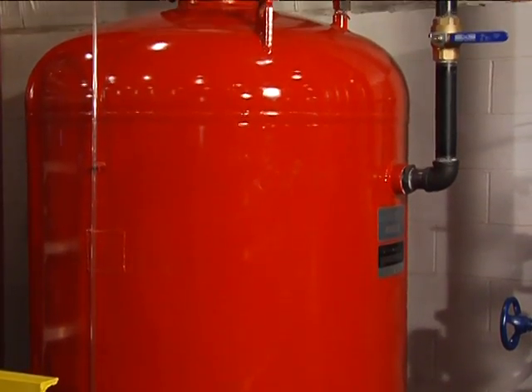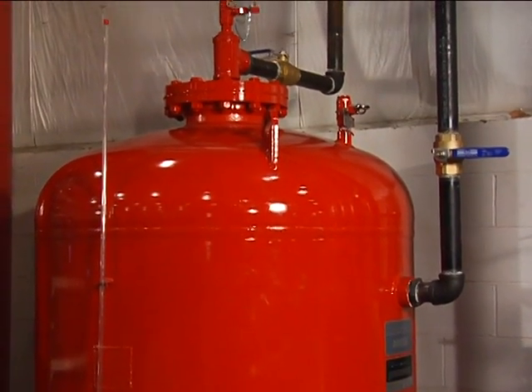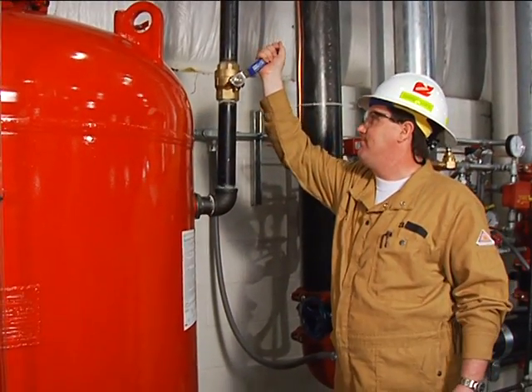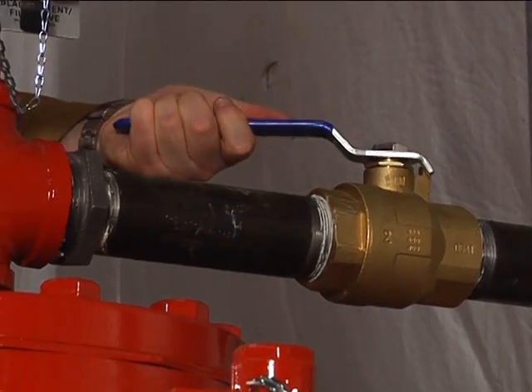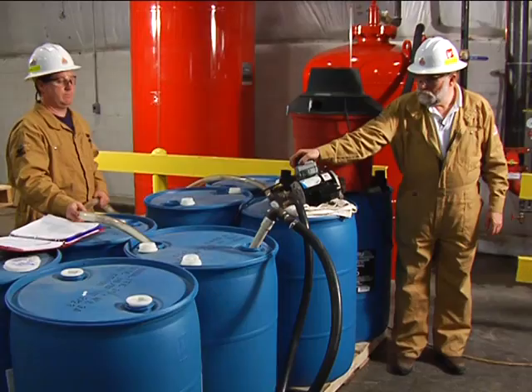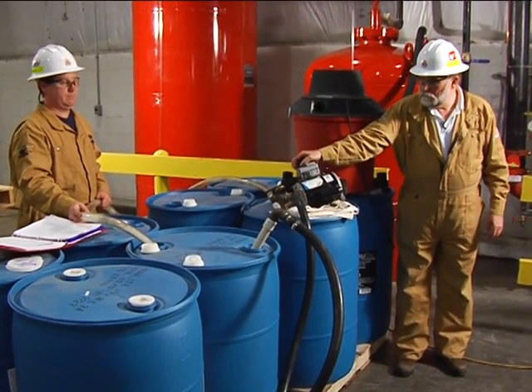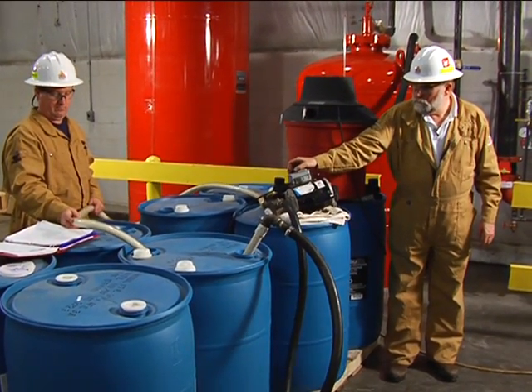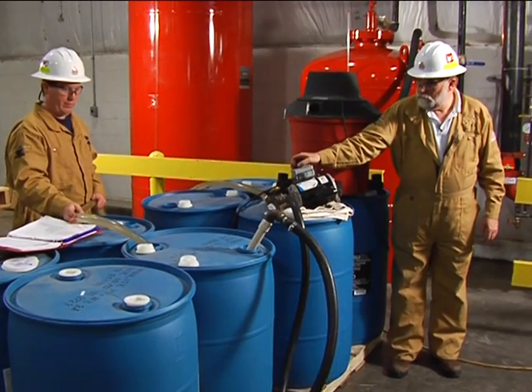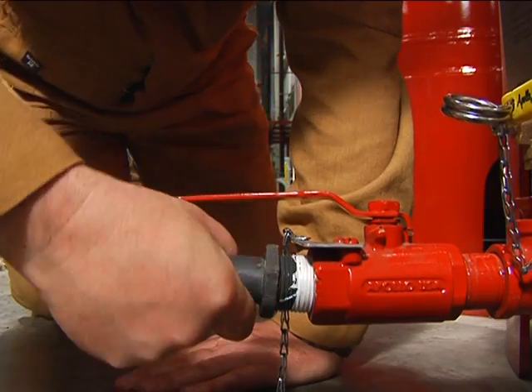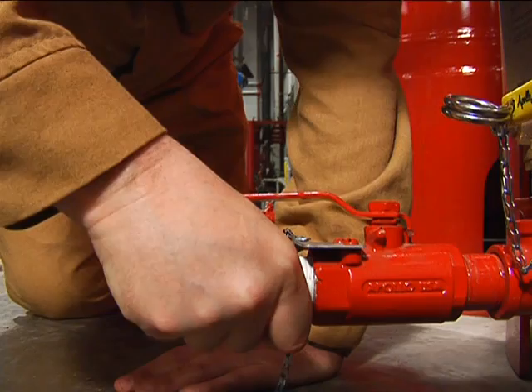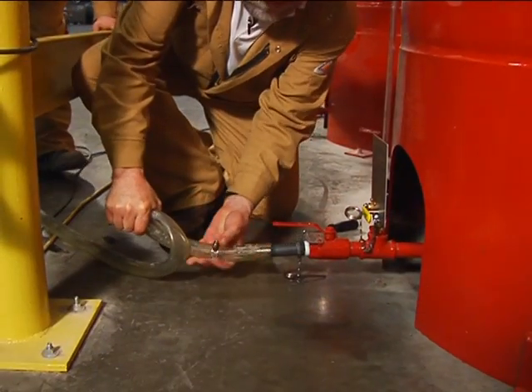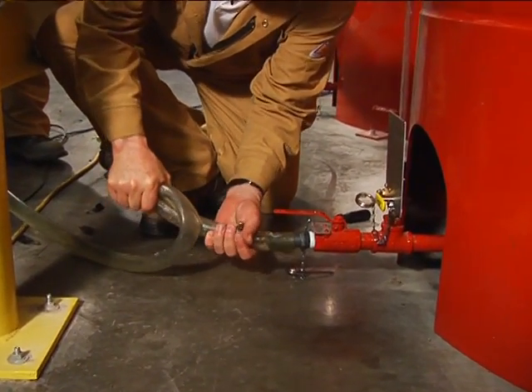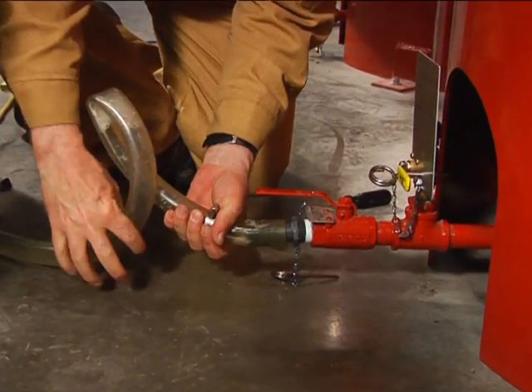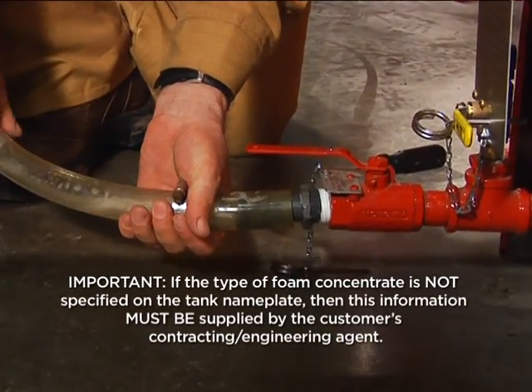Now you can partially refill the bladder tank. Make sure the water inlet valve and the concentrate isolation valve are closed. Open the pump valve and prime the pump with concentrate, then close the pump valve. Now connect the concentrate pump and valve to the bladder drain fill valve. Again, only the Ansul foam concentrate specified on the tank nameplate may be pumped into the bladder.